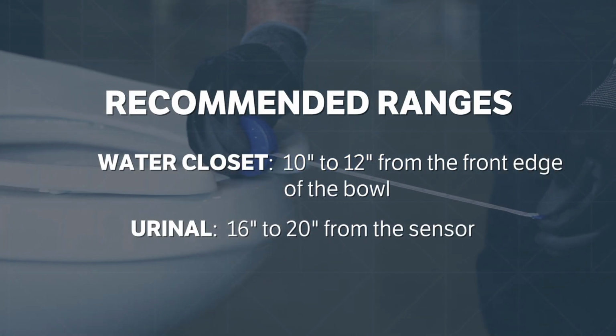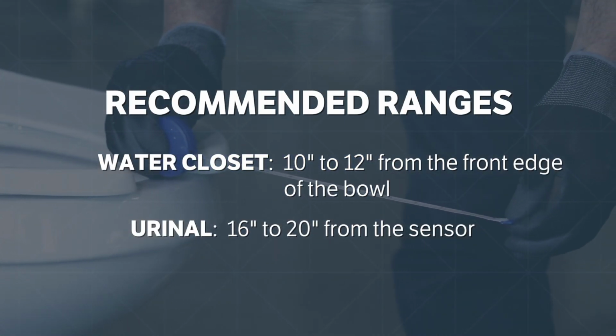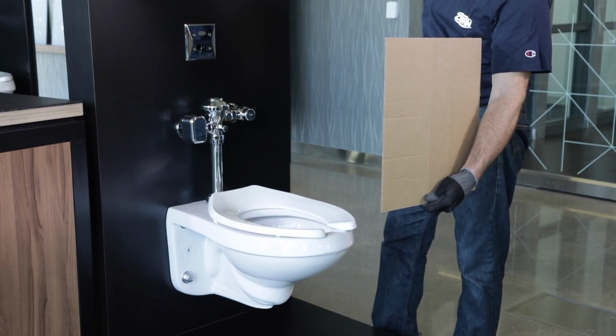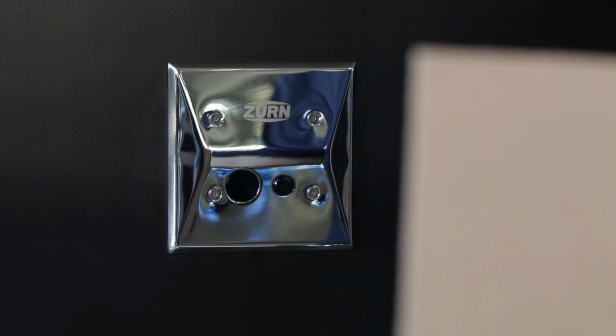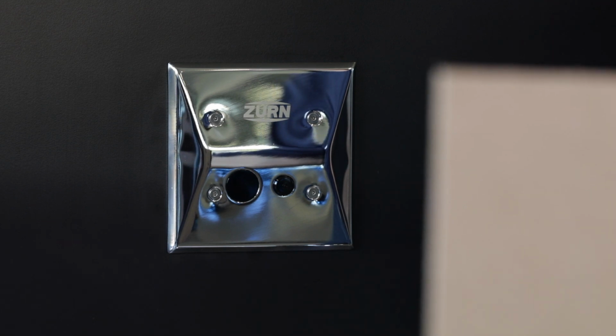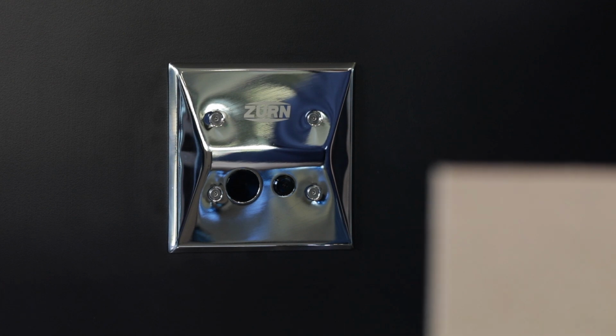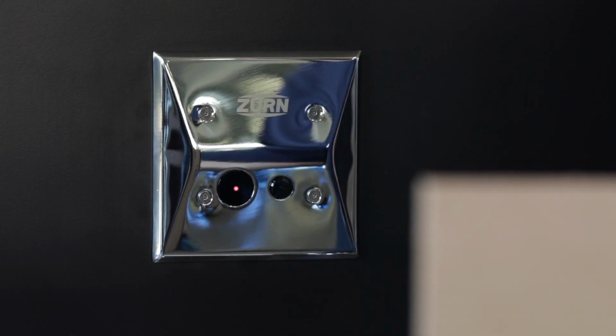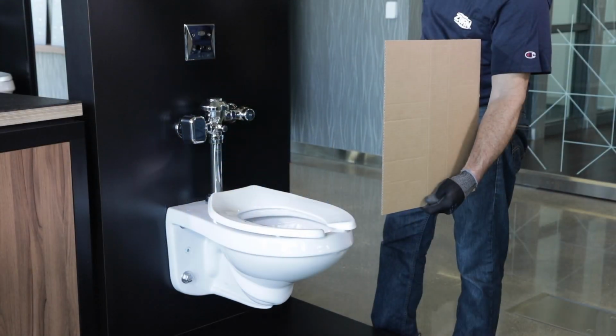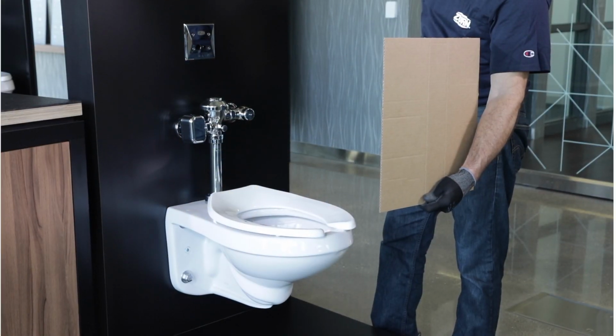Next, set the target. This should be no less than 16 inches from the sensor face. Double check that no other objects are in view of the sensor face. Keep the target steady. The sensor will blink while calibrating. After 30 seconds, calibration ends. You'll either see the LED blink quickly 2 times, or the LED will be solid for 5 seconds. A solid LED will require calibration again.